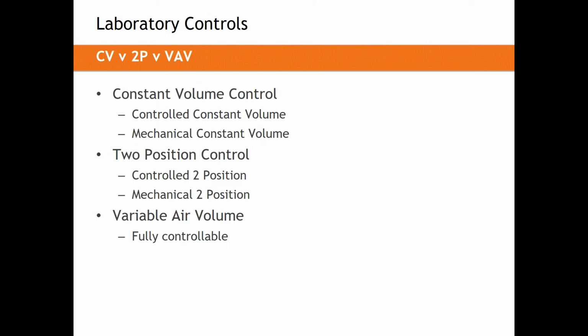On a Venturi valve, we can achieve mechanical two-position, meaning using a lower cost actuator and a set of relays, you can drive to a minimum position to a maximum position. Nothing exists in between those two settings. So if you're at 100 CFM at the minimum, you could flip a switch and drive open to 500 CFM, for example. You cannot achieve 400 without mechanically changing something about that actuator and its hard stops.